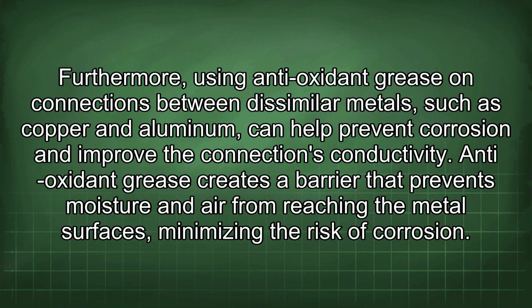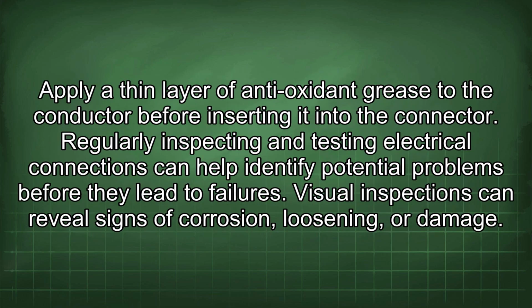Furthermore, using antioxidant grease on connections between dissimilar metals, such as copper and aluminum, can help prevent corrosion and improve the connection's conductivity. Antioxidant grease creates a barrier that prevents moisture and air from reaching the metal surfaces, minimizing the risk of corrosion. Apply a thin layer of antioxidant grease to the conductor before inserting it into the connector. Regularly inspecting and testing electrical connections can help identify potential problems before they lead to failures.